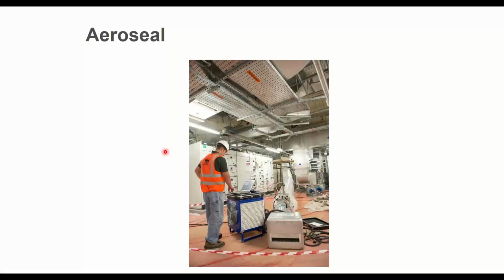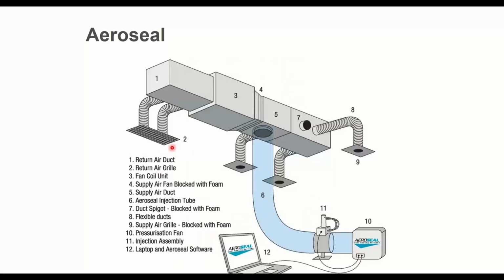All right, so the Aeroseal process. This is what it's going to look like. This is a pretty simple, small duct system for our example right here. So here's my duct system. Here's my main supply trunk. Number three is my air handling unit. It doesn't matter if it's a rooftop unit, an air handler, a fan coil, a residential furnace, whatever you've got. This number one side over here is my return side, and over here is my supply side of ductwork.